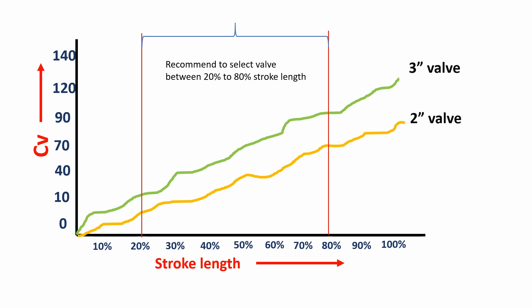So this is basically a hard and fast rule. Normally these manufacturers will recommend to select a valve that falls between 20 to 80 percentage of the stroke length for getting a good operating result.